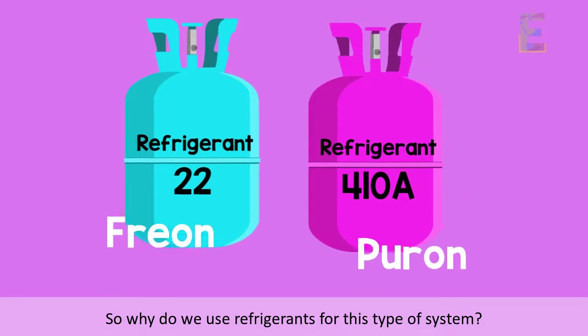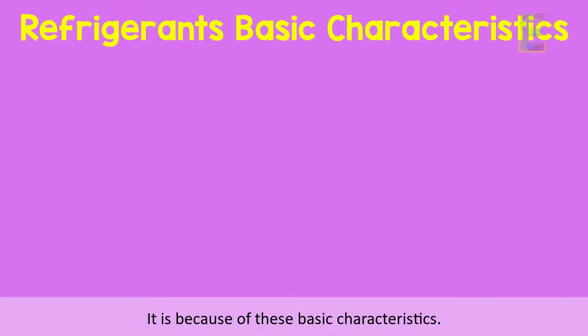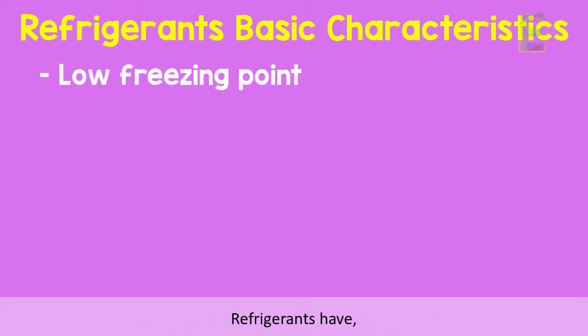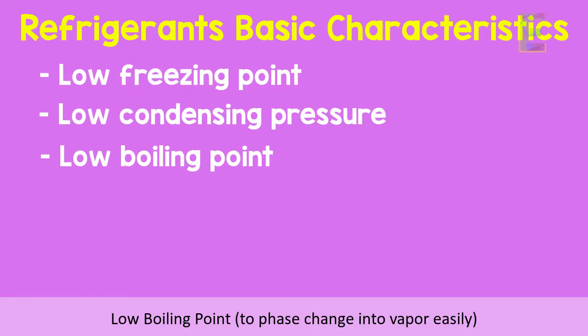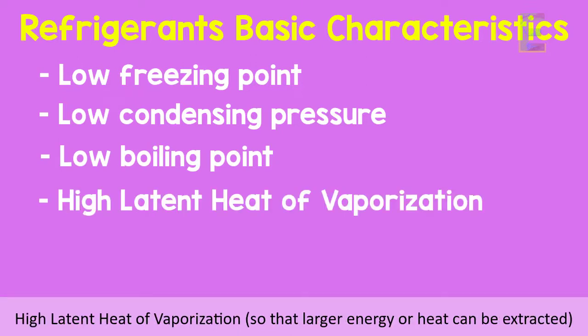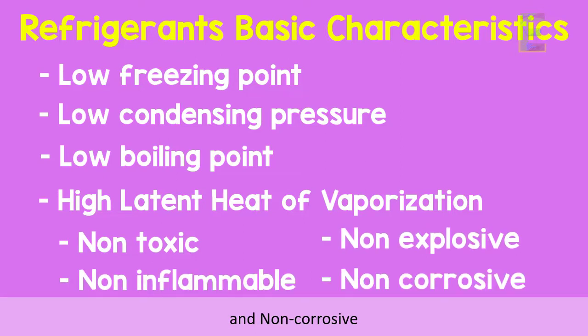So why do we use refrigerants for this type of system? It is because of these basic characteristics. Refrigerants have low freezing point, meaning it should not freeze easily. Low condensing pressure to condense easily. Low boiling point to phase change into vapor easily. High latent heat of vaporization so that larger energy or heat can be extracted. Of course, non-toxic, non-inflammable, non-explosive, and non-corrosive.